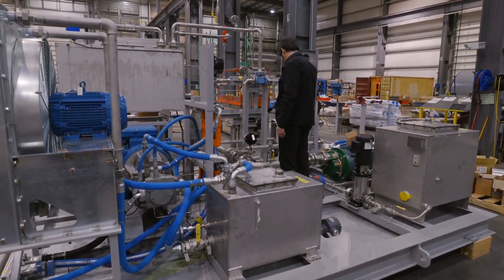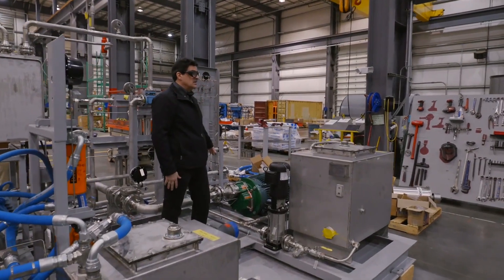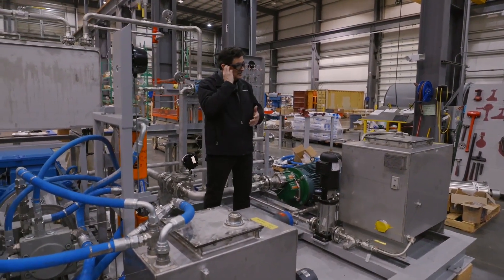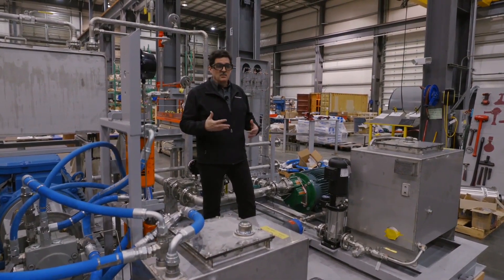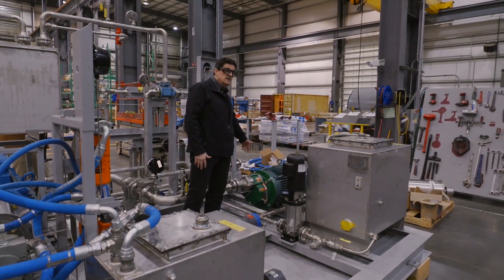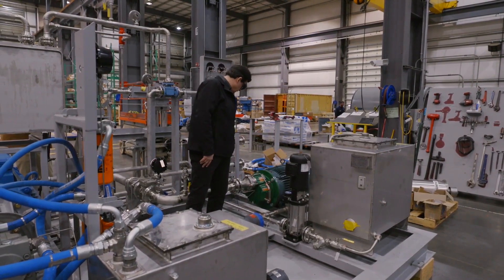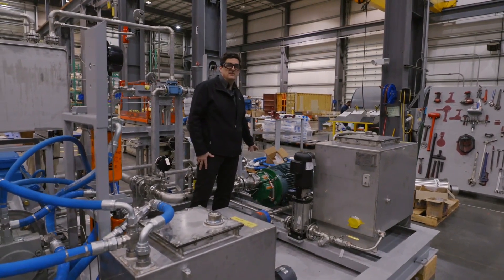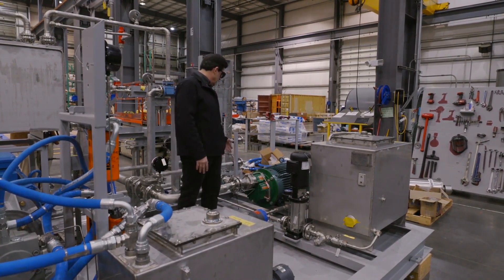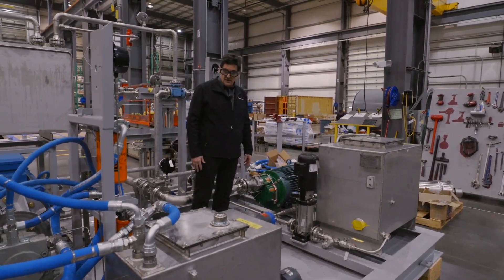All our turbine lube oil systems come with an oil-water separator to help reduce the water in the oil. We have our water wash system over here, and then our NOx water system. One of the things we did was redesign the NOx water system — on many sites it's a separate skid with a pump, gearbox, and motor, and the alignment and manufacturing of that was problematic with issues in the field. We've changed to a new system with an integral gearbox pump mounted right to the motor shaft. It simplifies it, makes it smaller, actually outperforms the old system, and was cheaper in the long run. This enabled us to get it onto the auxiliary skid, eliminate the other skid, and eliminate a bunch of alignment and leak issues, creating a much more reliable system.